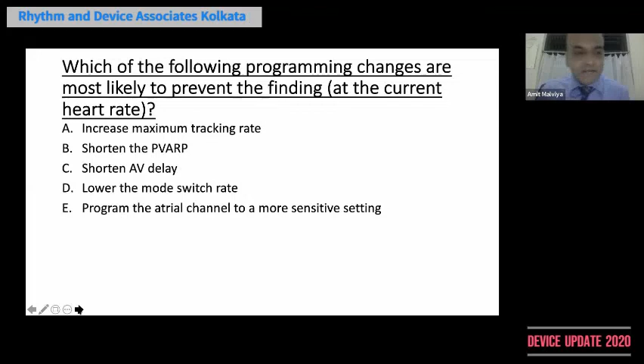In previous pacemakers, whenever the heart rate increased above a certain limit, they used to go into 2:1 block. So there was a precipitous fall of heart rate, which used to become symptomatic. Sometimes the patient used to complain of lightheadedness. Now this new algorithm, which manifests as a Wenckebach phenomenon on ECG, and which typically causes pseudo pacemaker Wenckebach, works like this: whenever the heart rate goes towards the MTR, the maximum tracking rate, the pacemaker automatically prolongs the AV delay so as to stop the phenomenon of 2:1 AV block.